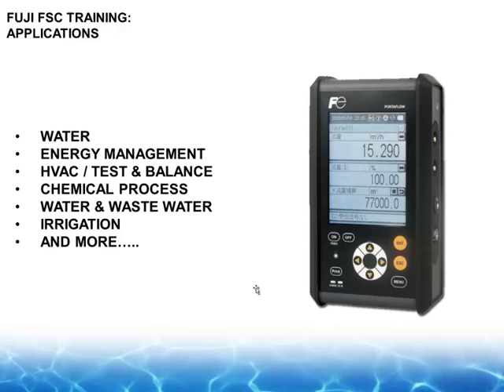And again, sludge. What's sludge? Sludge is, ever have oatmeal for breakfast? That's sludge. Sludge is traditionally high solid bearing applications that you use, say, in the pulp and paper industry, the mining industry, the dredging industry, and so on. Those are the kind of applications that are not that common. Those would be served better by an ultrasonic Doppler flow meter. In this case, if it's a liquid application, there's a 98% chance it's a transit time type technology application. So I said water, energy management, HVAC, chemical process, wastewater, food, irrigation, and the list just goes on and on and on. Closed pipe full of liquid, petrochemical industry, doesn't make any difference.